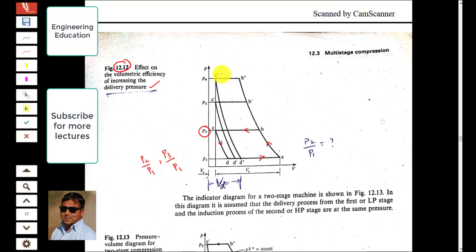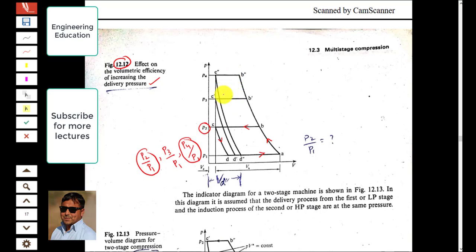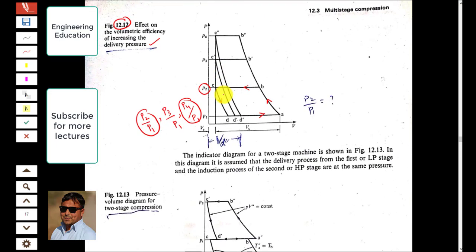For cycle A-B''-C''-D'' the pressure ratio is p4/p1. For the lesser pressure ratio we have high volumetric efficiency, while for the higher pressure ratio we have less volumetric efficiency. It is very clear from the diagram that by increasing the pressure ratio volumetric efficiency decreases, and if we reduce the pressure ratio volumetric efficiency increases.